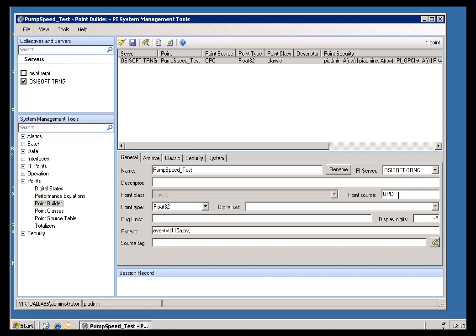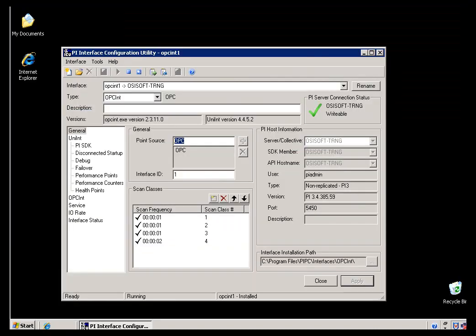Sometimes, if it won't hurt production, what you'll see people do is go over to the Interface Node and simply stop and restart the Interface. That way, we'll go ahead and start scanning all the tags all at once.